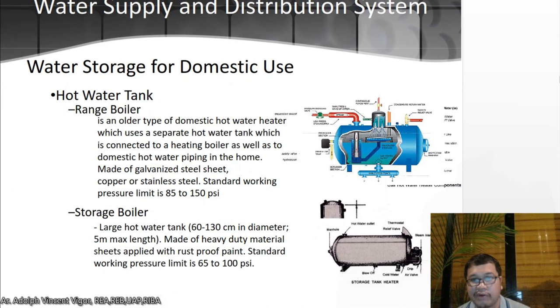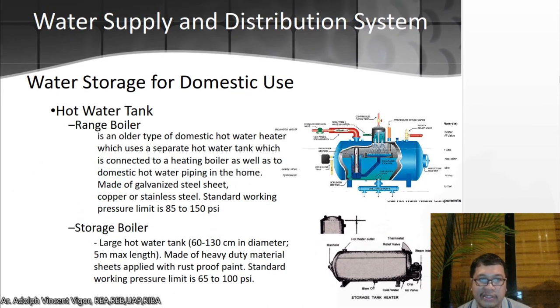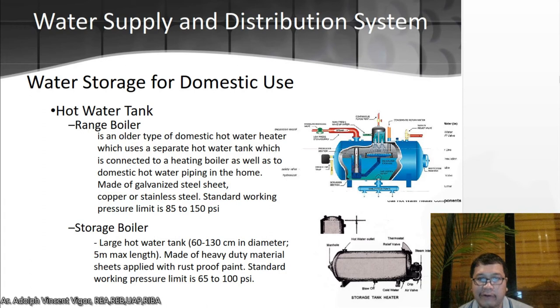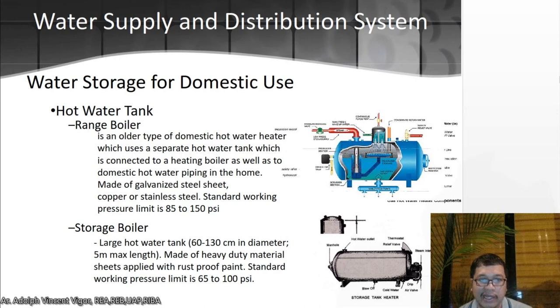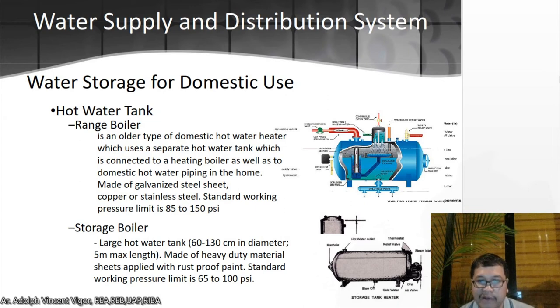For water storage for domestic use, there is the hot water tank versus the range boiler. The range boiler is an older type of domestic hot water heater connected to a heating boiler and domestic hot water piping. It's made of galvanized steel, sheet copper, or stainless steel, with a standard working pressure limit of 85 to 150 psi. The storage boiler is a large hot water tank 60 to 130 centimeters in diameter with a maximum of five meters in length, with a standard pressure limit of 65 to 100 psi.